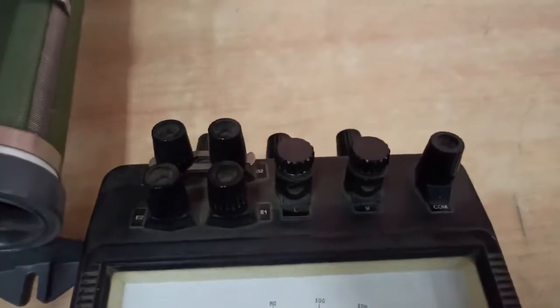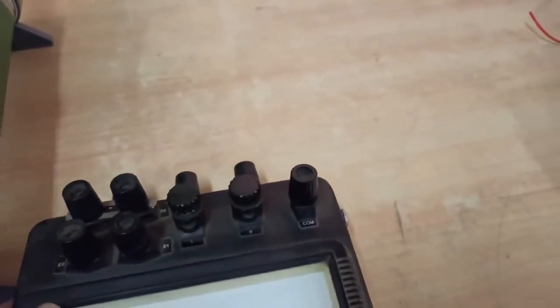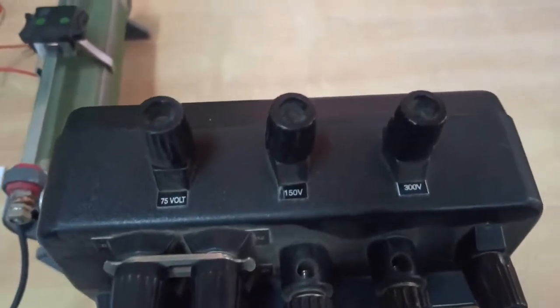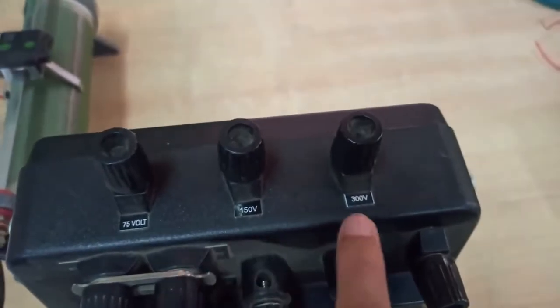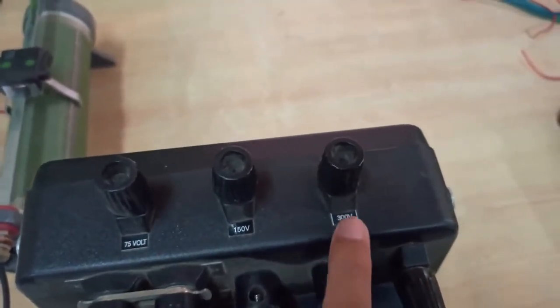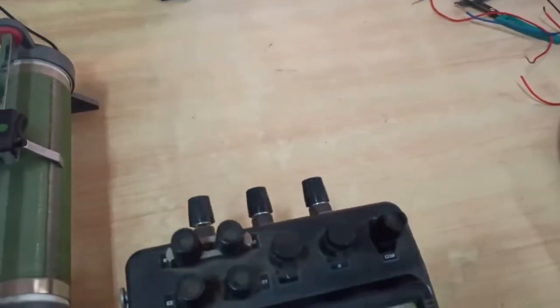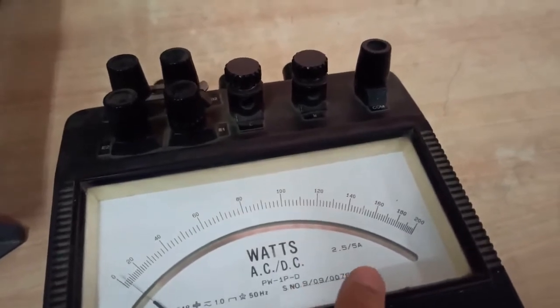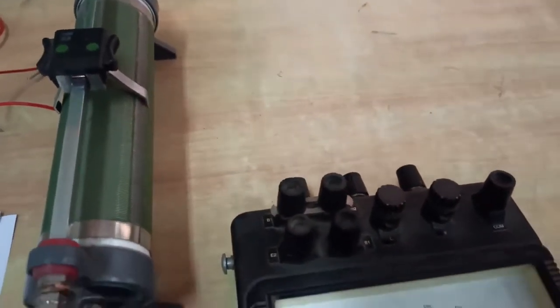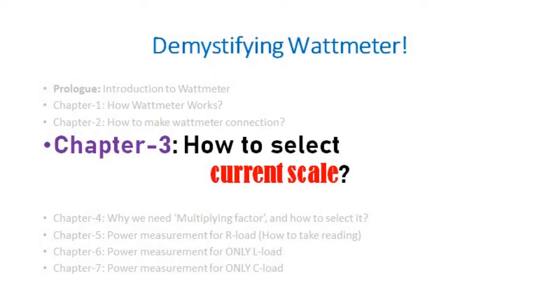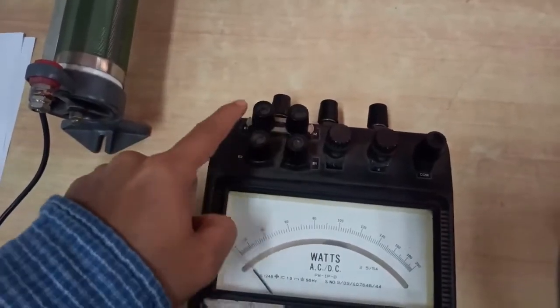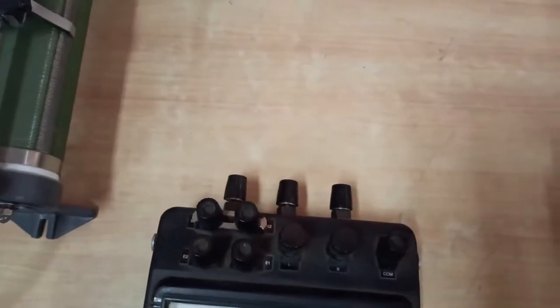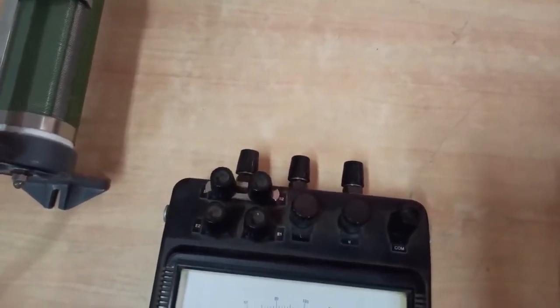For voltage measurement, we have three ranges available. Just as a voltmeter may have two or three ranges, the wattmeter also has three voltage ranges, and you select one based on your requirement. For current, we have two ranges: 2.5 A and 5 A, shown on the display. You select these by making proper connections at the terminals. Currently it is set for the 2.5 ampere scale.